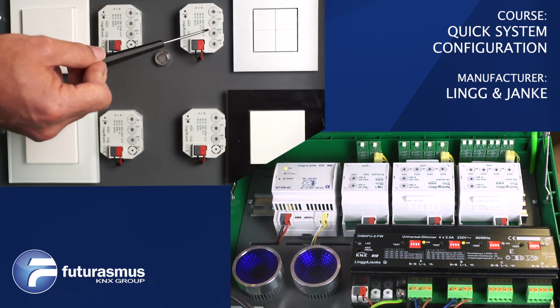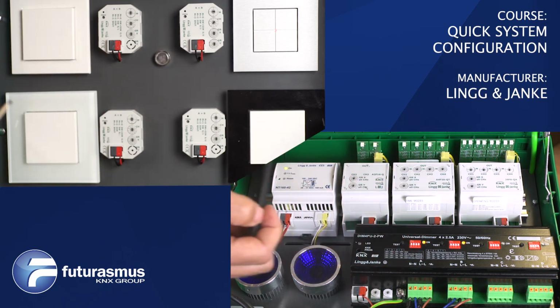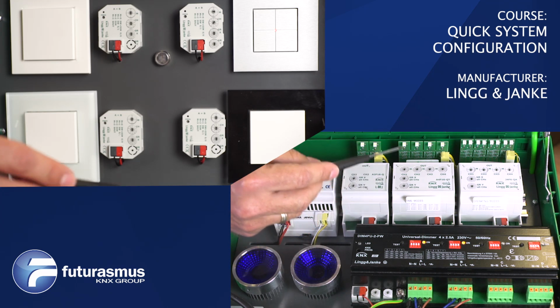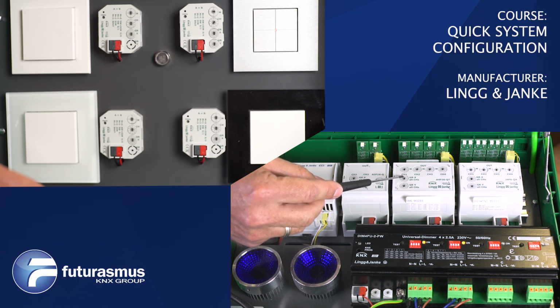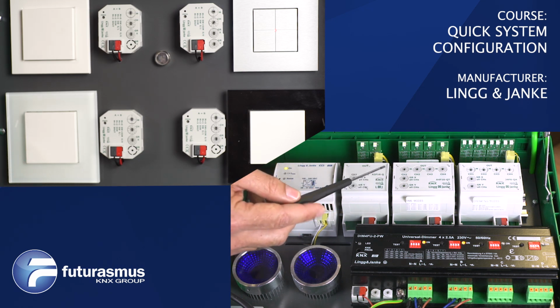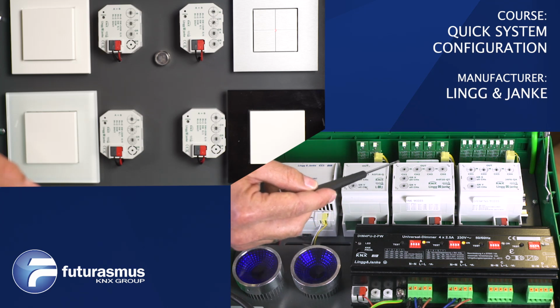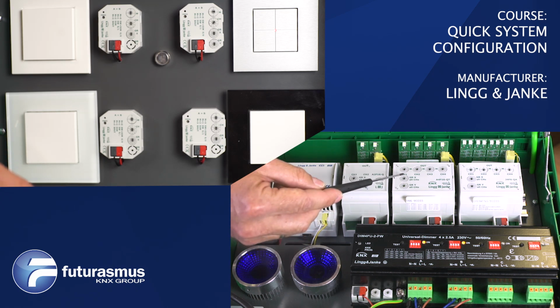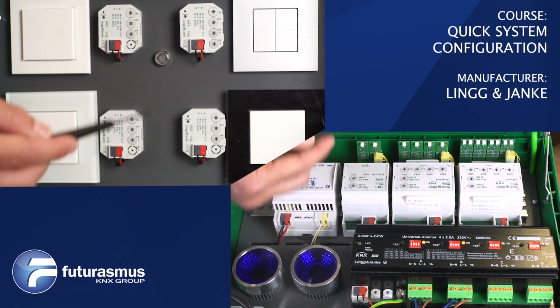It doesn't really make sense in the push button to use both groups, but in the actuator it makes more sense, because there you can have the sending group address and the listening group address. The sending group address is also used for listening. If you are familiar with KNX, you would know that an object can only send one group address to the bus. In this case, it can listen to various. So in this case, the X and the Y will both listen to this command.